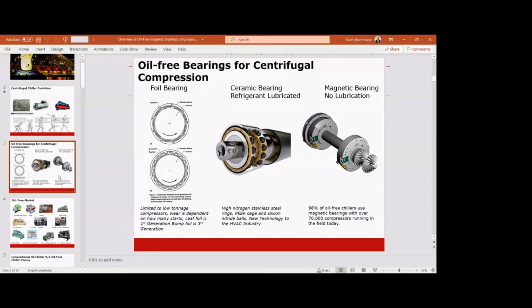One of the limitations is the weight of the shaft or the capacity of the compressor. So the delta P, or the difference between the high side and low side of the refrigeration system, creates the pressure to lift the shaft. So if the shaft is too heavy, we won't have enough pressure ratio to lift the shaft. So there are some limitations. Also, on every startup, we actually start on the bearing. So the bearings do have a limitation on how many starts and stops they can have in a lifetime.